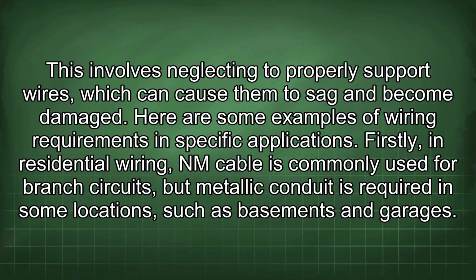Here are some examples of wiring requirements in specific applications. Firstly, in residential wiring, NM cable is commonly used for branch circuits, but metallic conduit is required in some locations, such as basements and garages.